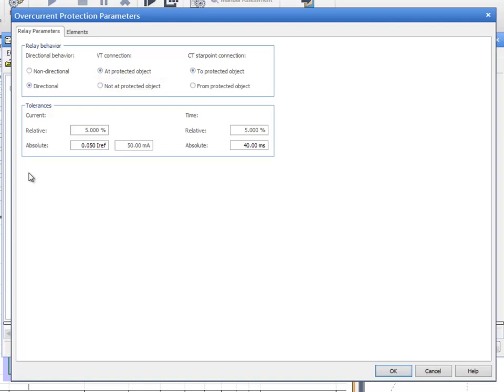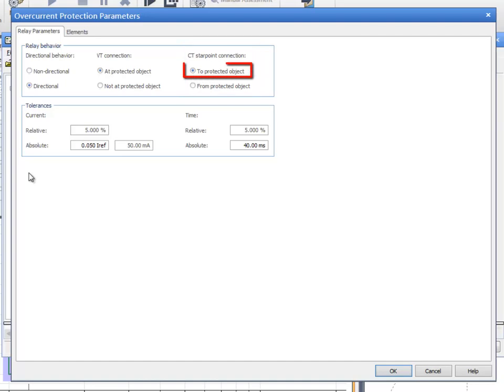The same theory applies for the CT connection. Select To Protected Object when the CT start point is connected on the line side. This means that the currents generated by the CMC test set are in phase with the currents that the primary network would have.